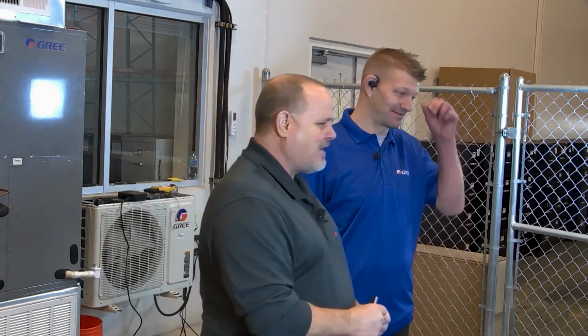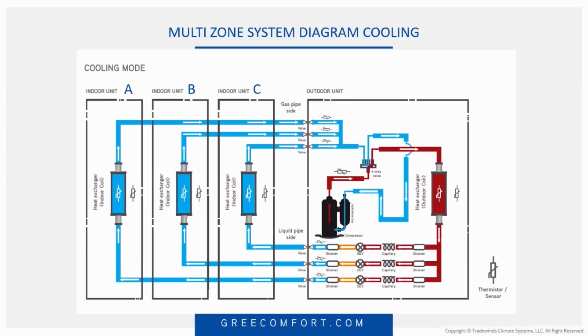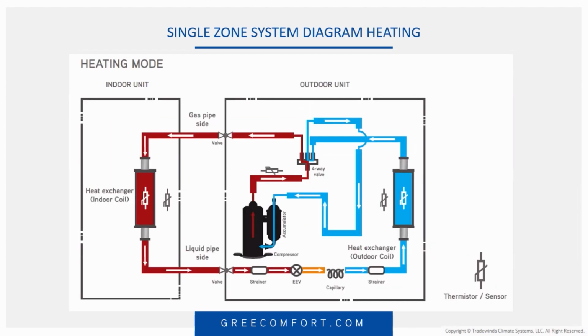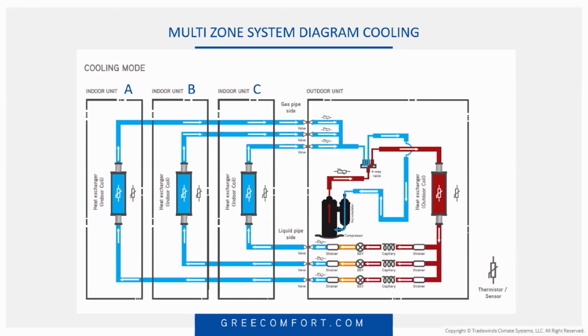We want to get in, we want to troubleshoot that unit, and we want to get out. But you can't always win that war. You've got to give these machines time to think. But once you understand that and you move forward with that, it's not as difficult as it sounds. So now let's get into multi-zone. Again, I said if you understand the basic refrigeration circuit, which is what a single zone system is, you can understand a multi-zone.